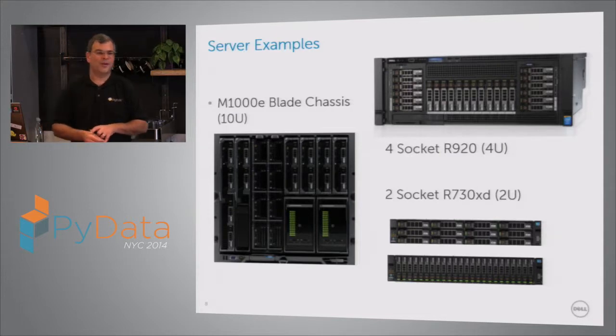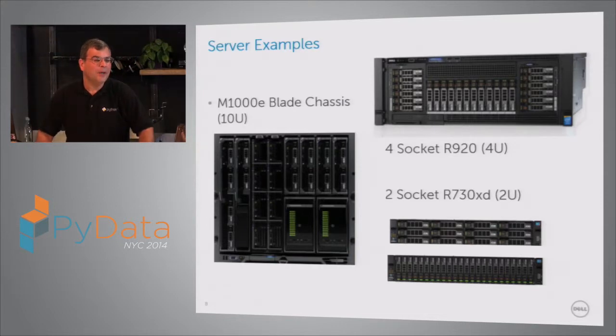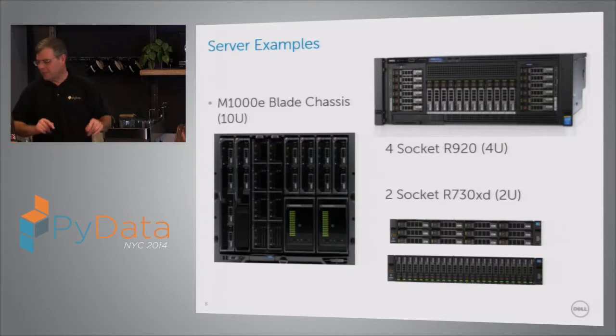I can't quote prices on a video, but how much power? That particular cluster needs about 30 amps at 208 volts for every rack. It's very, very dense configuration. Talk to me about pricing later. I'm not going to get in trouble quoting pricing on a video because it'll go viral, trust me.